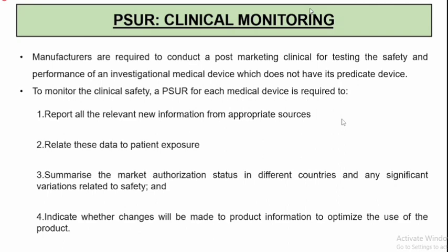And to monitor the clinical safety, a PSUR for each medical device is required to do all these 4 steps, which include: report all the relevant new information from appropriate sources, relate this data to the patient exposure, summarize the market authorization status in different countries and any significant variations related to safety, and indicate whether changes will be made to product information to optimize the use of the particular product.